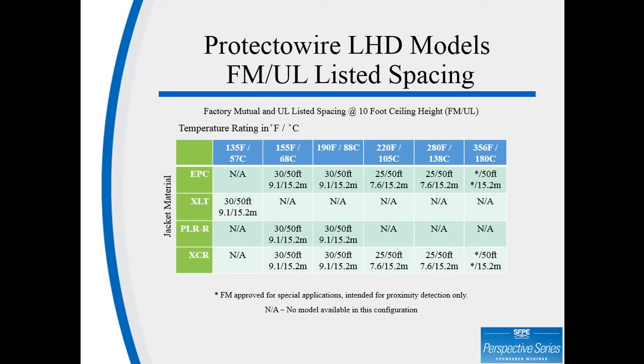Listed spacings. All heat detectors and smoke detectors have listed spacings to assist the designer in properly applying the product. This chart shows the different jackets for our digital LHD. It also shows the different temperatures that we offer. If you follow along to the first one, that says EPC and 135 degree, of course we have in there that it's not available because we do not make the 135 in an EPC jacket. If you go down one row, you'll see that it's made in an XLT jacket, which is good to 60 below. And the listed spacing at FM is 30 feet on centers, and of course at UL, 50 feet on centers. We've shown those values in metric, just slightly below that.